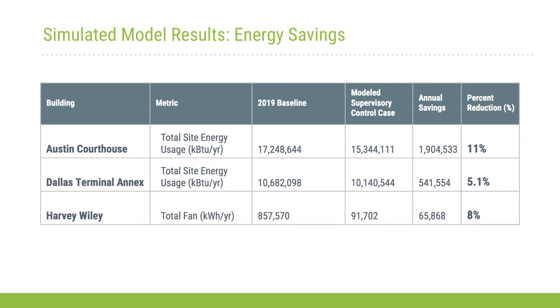A little bit on the process: the occupancy sensors were installed prior to the COVID-19 pandemic, and actually the curve of occupancy stayed the same - just the amount of people was reduced. The times people entered and left the building stayed the same, just fewer people. We used that information to input into the vendor's product for the optimized start and stop times, as well as the midday ramps and end of day ramps. That is where a lot of savings was found in all three buildings.